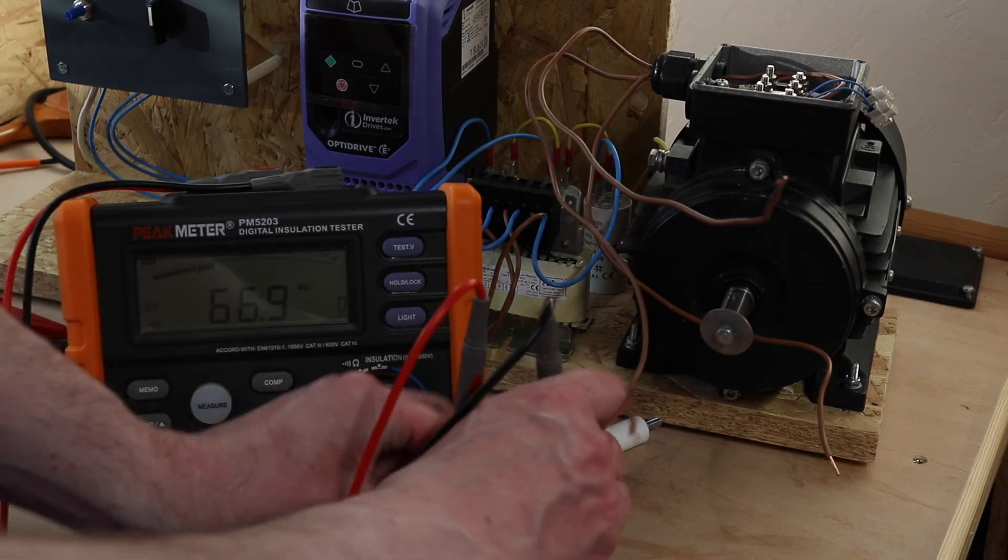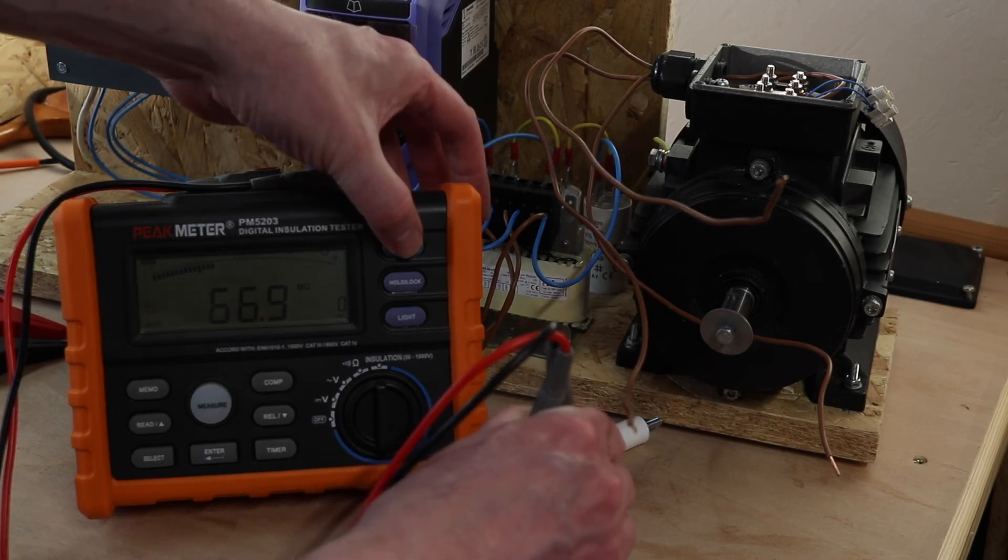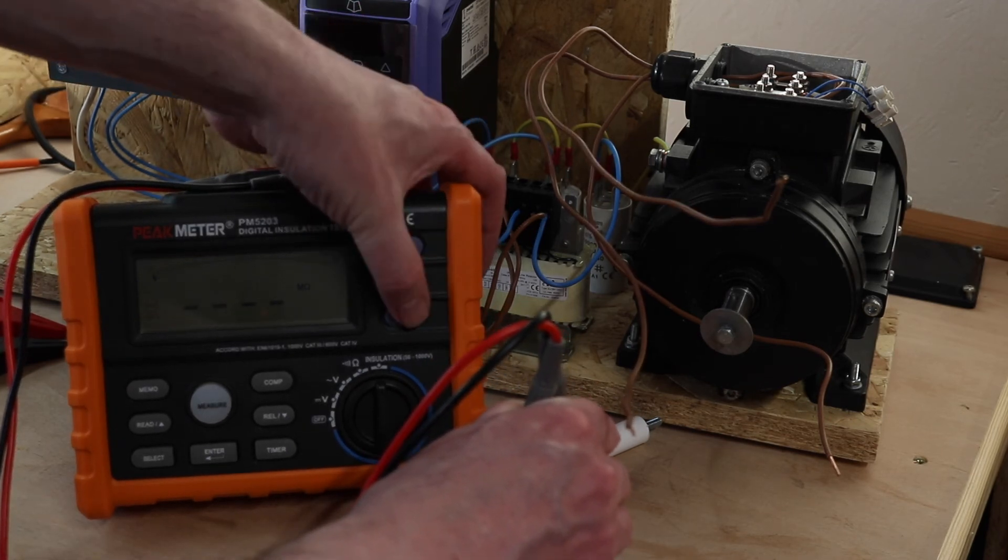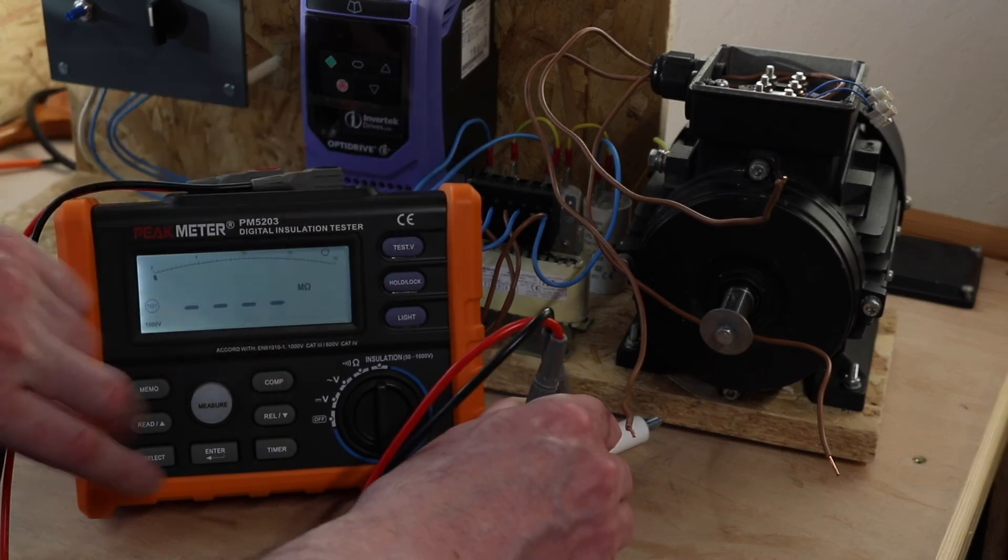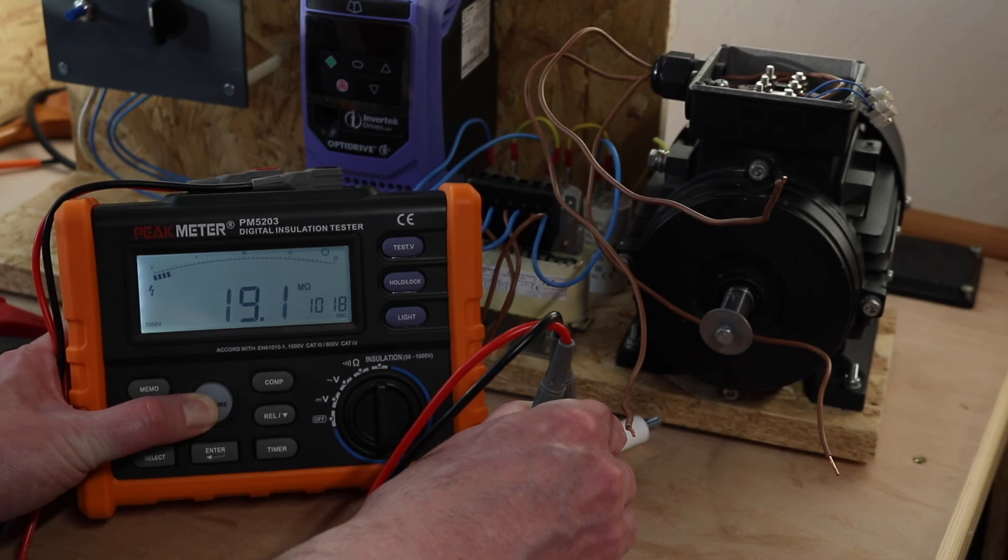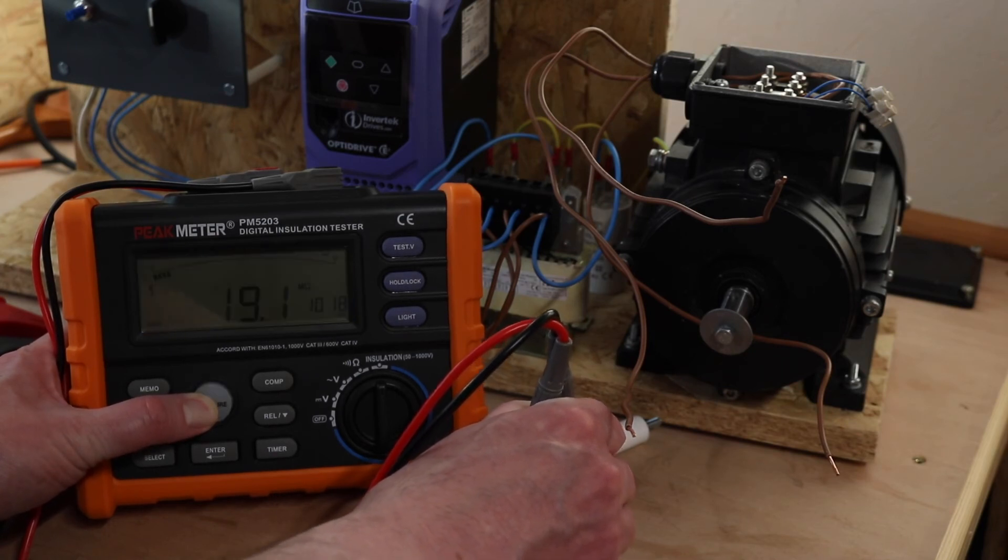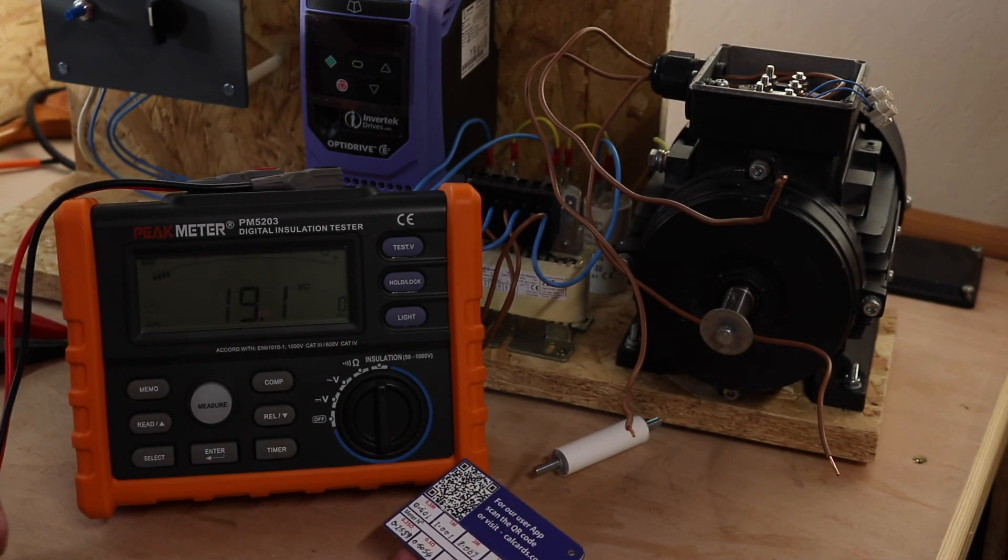Right back on again, the go button. You see I've got a 19.1 mega ohms reading there. I've verified this on an instrument, so the actual value is 19.86, so pretty much there with this.